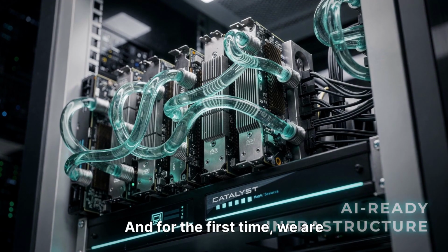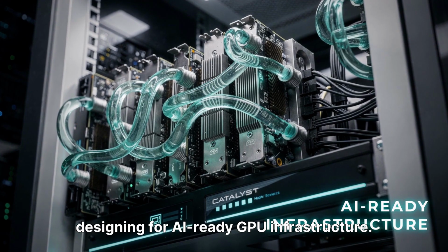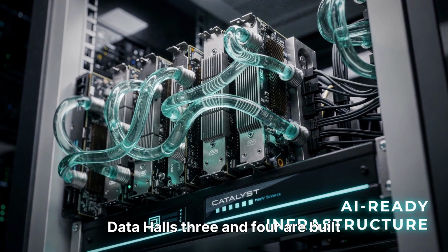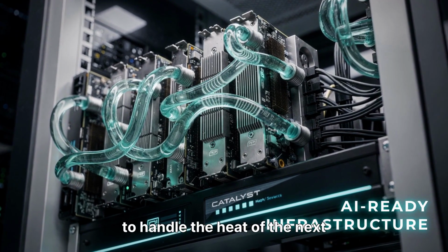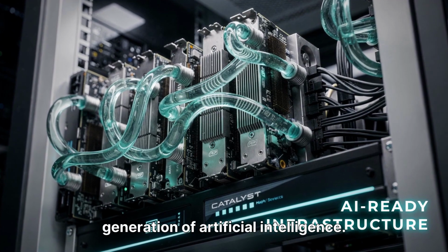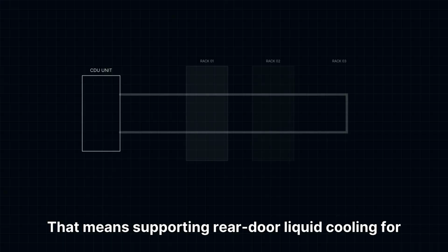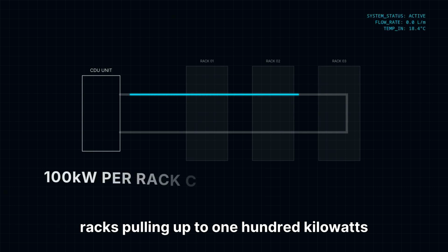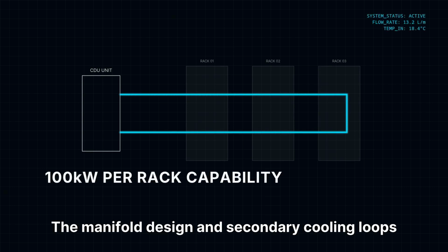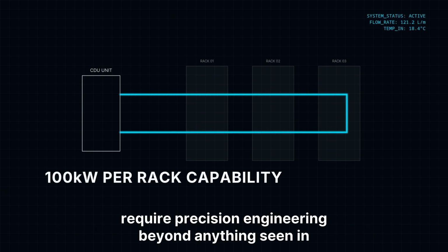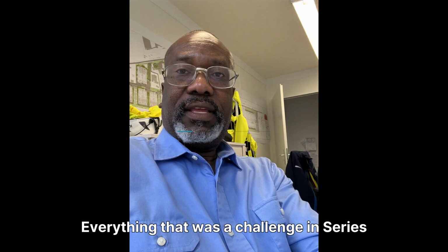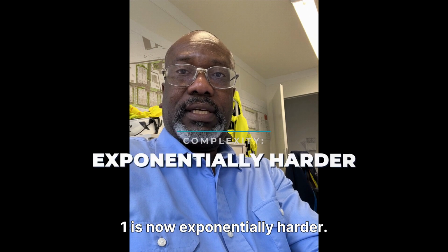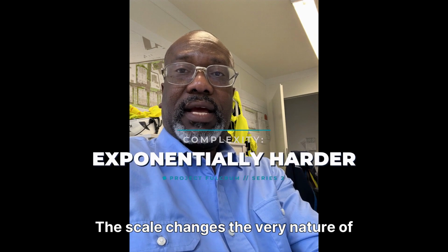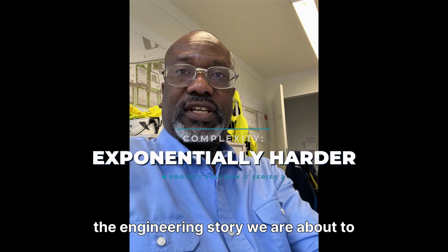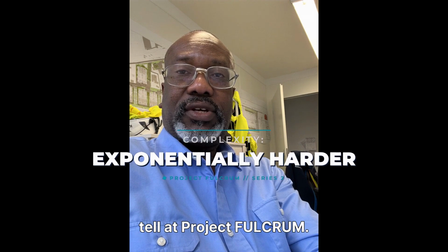And for the first time, we are designing for AI-ready GPU infrastructure. Data halls 3 and 4 are built to handle the heat of the next generation of artificial intelligence. That means supporting rear door liquid cooling for racks pulling up to 100 kilowatts each. The manifold design and secondary cooling loops require precision engineering beyond anything seen in Series 1. Everything that was a challenge in Series 1 is now exponentially harder. The scale changes the very nature of the engineering story we are about to tell at Project FULCRUM.